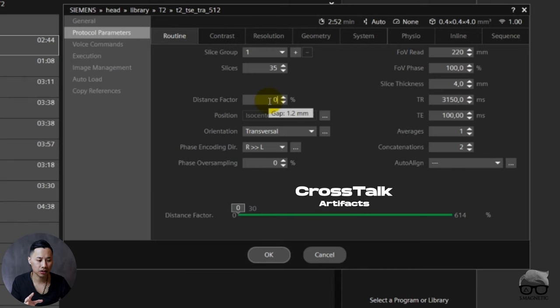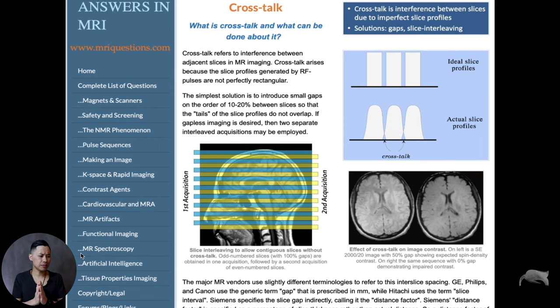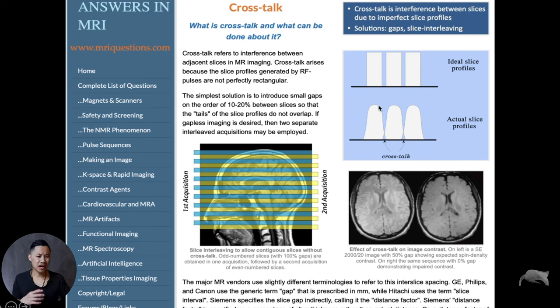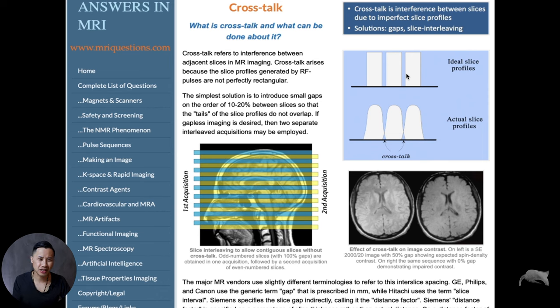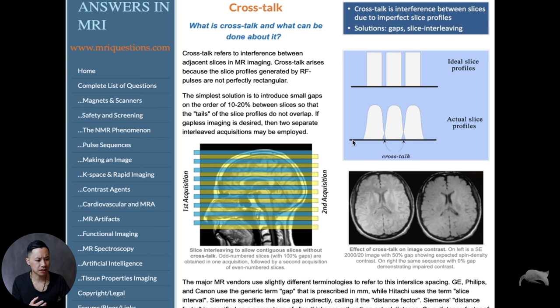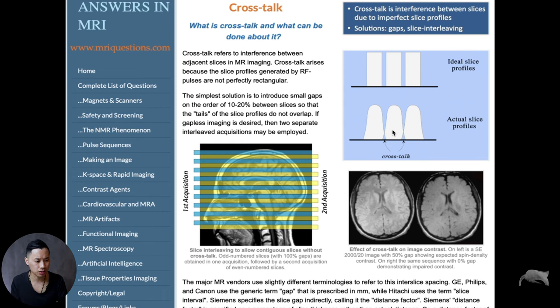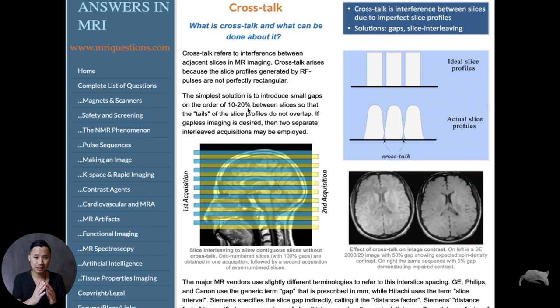So what is crosstalk? Let's check this out. You can find more information regarding this topic at mrquestions.com. How can we avoid this? The ideal slice profile, like this nice peak, slice one, slice two, slice three, that's not the real deal. That's not how it happens in real life. Actual slice profile takes time to come up, takes time to go down. Another slice again, another slice has a little bit tail here which crosses between slice one and slice two, which gives you this crosstalk artifact. Simple solution for avoiding this is to have 10% or at least 20% of slice distance factor to avoid this because then you will shift the tail away from each other so you won't get this crosstalk artifact.